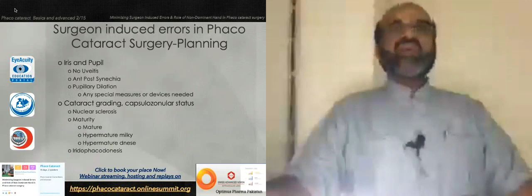And then you have to grade the cataract. As I mentioned before, the ideal cataract to emulsify is not too soft and not too hard. A too soft cataract is difficult to crack. It will give way. You know the vacuum which we discussed in our previous discussion, the vacuum builds up only when the tip is occluded. If the cataract is too soft, it will be difficult to build that vacuum. And if the cataract is too hard, you will need extra phaco energy, and the risk of corneal burn and endothelial damage will increase.